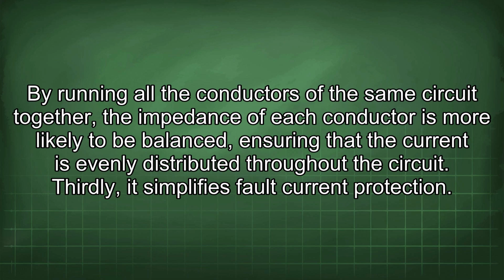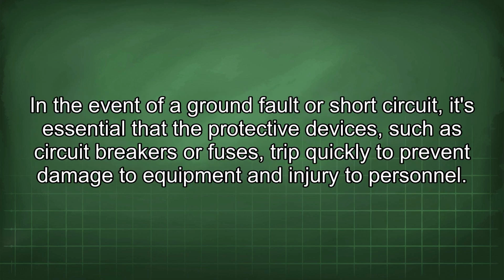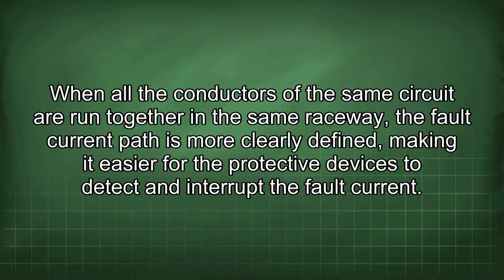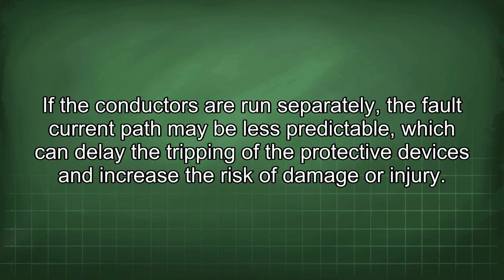Thirdly, it simplifies fault current protection. In the event of a ground fault or short circuit, it's essential that the protective devices, such as circuit breakers or fuses, trip quickly to prevent damage to equipment and injury to personnel. When all the conductors of the same circuit are run together in the same raceway, the fault current path is more clearly defined, making it easier for the protective devices to detect and interrupt the fault current. If the conductors are run separately, the fault current path may be less predictable, which can delay the tripping of the protective devices and increase the risk of damage or injury.